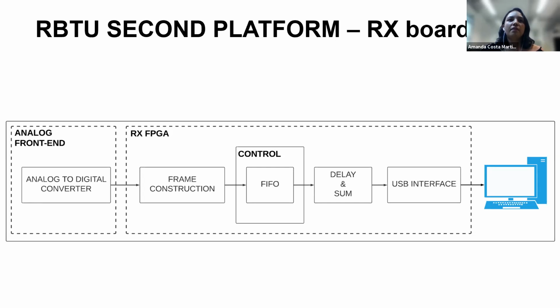After all this process, it is possible to send the data to the delay and sum module. In the delay and sum stage, the data is being formed according to the delays configured by the user. And this module receives 32 data samples simultaneously, and after processing, a single 16-bit data sample is sent to the interface module.